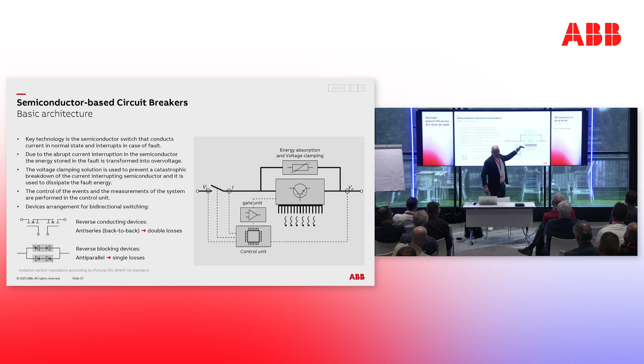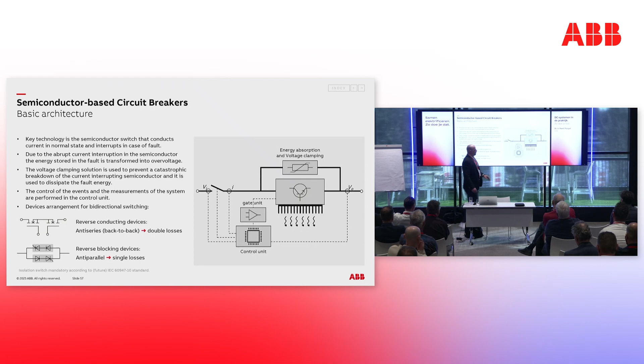And already it looks like a sort of converter with a very weird duty cycle, so you will probably end up with the very same requirements on the control and measurement as you have in any other power electronics converter. What you don't have in converters is the need for an electromechanical switch. It is still supposed to be a circuit breaker. A circuit breaker should give you safe operation. You cannot rely purely on a semiconductor to give you galvanic isolation. You somehow have to add it.